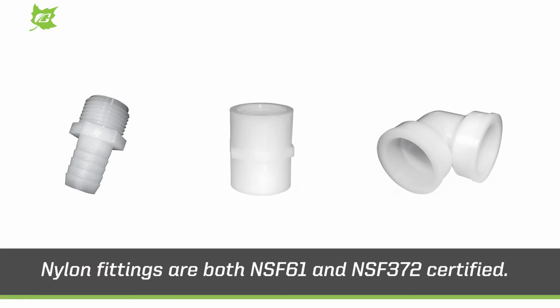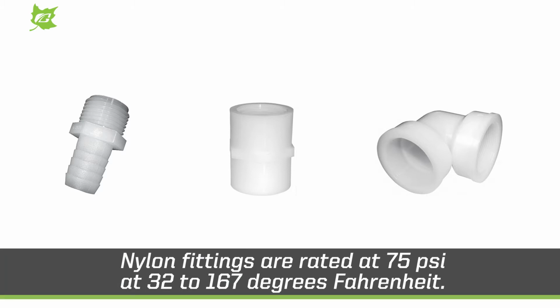Greenleaf's nylon and polypropylene hose, pipe, garden hose, nozzle, and heavy-duty fittings are manufactured in sizes ranging from 1/8 inch to 3 inch. Nylon fittings are both NSF 61 and NSF 372 certified. The pressure rating of the nylon fittings is 75 PSI from 32 to 167 degrees Fahrenheit. Polypropylene fittings are not NSF 61 or NSF 372 certified. The pressure rating is 75 PSI from 32 to 140 degrees Fahrenheit. Both nylon and polypropylene fittings are highly durable and chemical resistant and offered in a variety of thread and hose shank combinations.